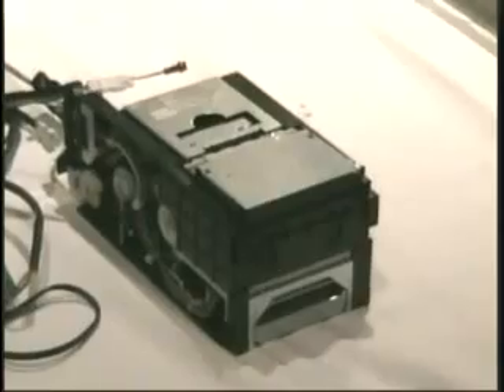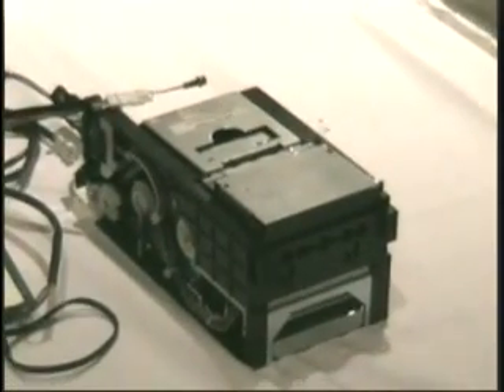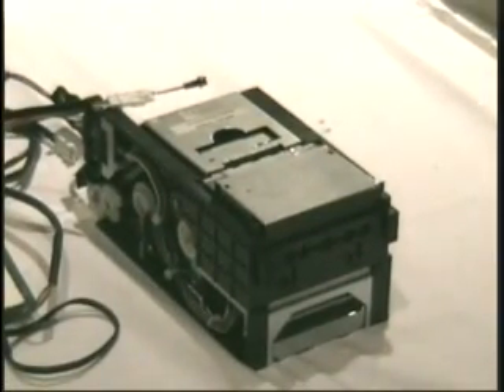Is there a set time limit or number of times that you push that paper in and out? No. I've seen it do it in as few as 3 tries. I've seen it take as many as 15 and not complete calibration the first time around. Basically, it depends on how far out it was, because when it's making those adjustments, changing that voltage, it's doing it in very small increments. So depending on how far out it was, it may do it 3, 4, it may take 10, 12. I've actually had some of them where it didn't calibrate the first time, reset power, try it again, and it will complete the calibration on the second.